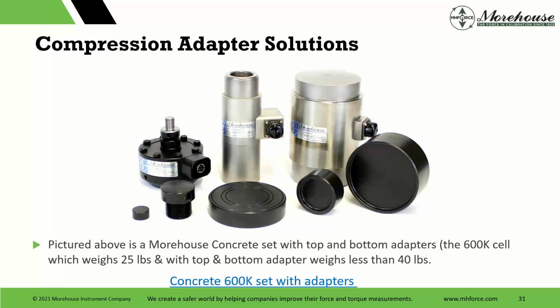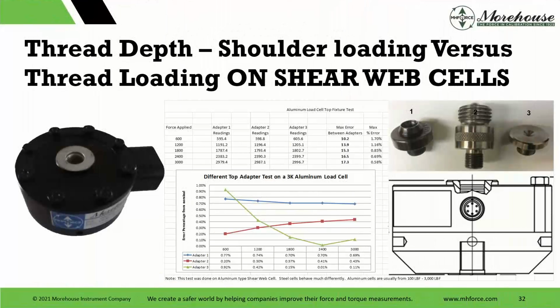So another thing, this is our concrete kit with top and bottom adapters. You want the bottom adapters because if you have female holes in the bottom of the cell, it's going to mark the platen. And the last thing you want to do is go into calibrate a customer's machine and mark it up. If you buy one of our Universal Calibrating Machines, you want to have adapters to protect it, because as soon as you mark things up, you get uneven surfaces, which are no good. So this is a set that has everything with it to protect machines.